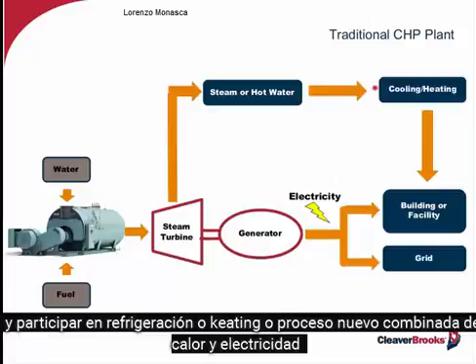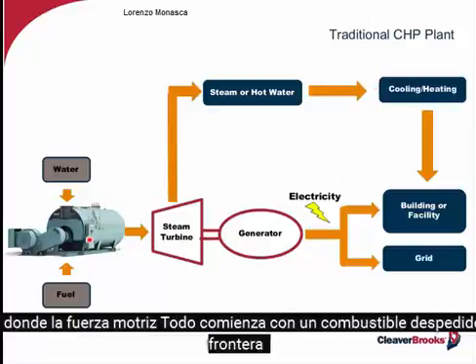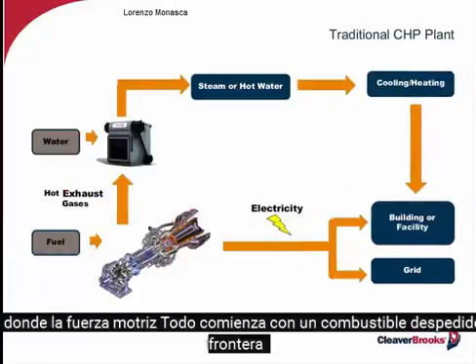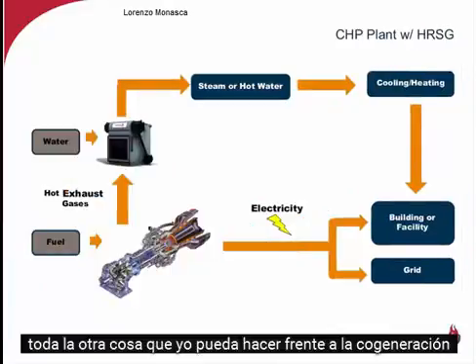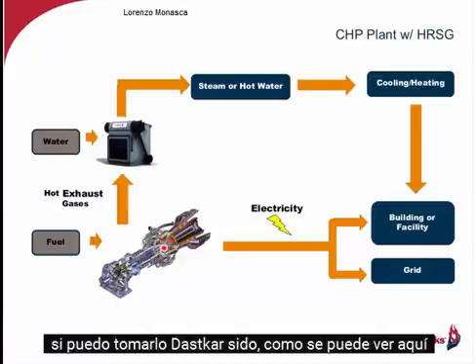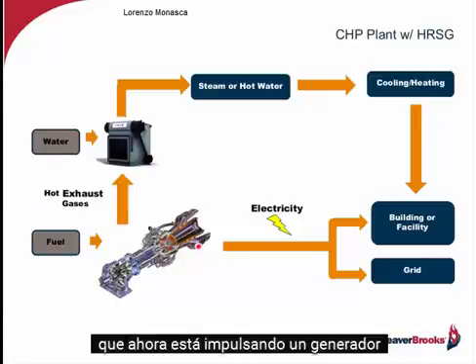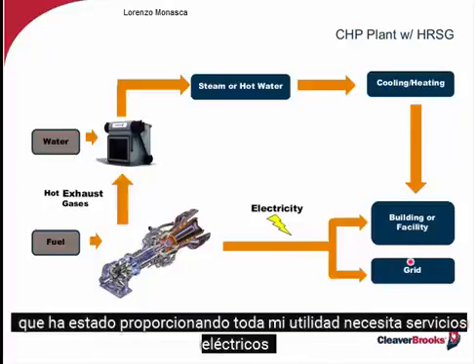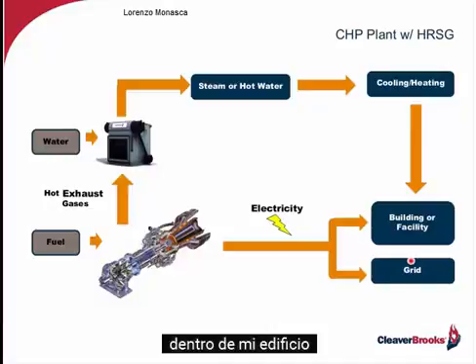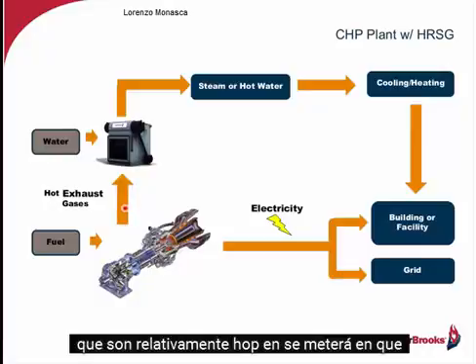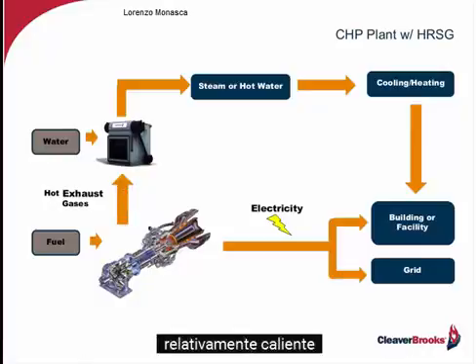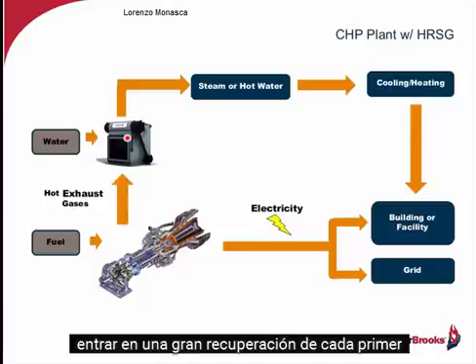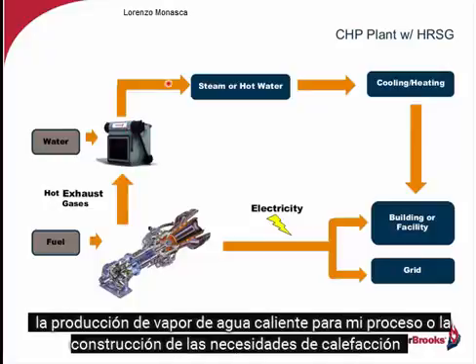Again, combined heat and power, where the motive force all begins with a fuel-fired boiler. Now, the other thing that I can do with combined heat and power is I can take a gas turbine, such as you see here, which is now driving a generator, which is then providing all of my electrical utility needs within my building, and I'm taking the off gases now, which are relatively hot, and we'll get into that, relatively hot, going into a heat recovery, HRSG, producing steam or hot water for my process or building heating needs, comfort heating or cooling.